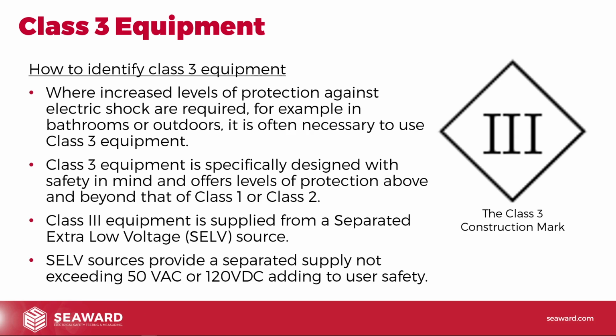Class 3 is very rare, and you are very limited on the tests you can carry out on Class 3 as well. There's not a lot you can do other than a very good visual inspection really, because the level of protection means there's not a lot there for us to test. There's no earth, for example, and that sort of thing. So Class 3 is quite rare.